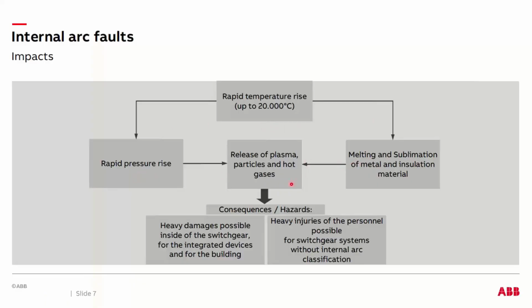So, both these lead to the release of plasma, hot gases and debris. If you have arc resistant equipment, you can channel them safely through the plenum on top of your switchgear and then run it outside of your PDC building or any house. In other cases, with non-arc resistant equipment, it could lead to potentially life-threatening injuries to the personnel standing in front of the equipment during such an event.